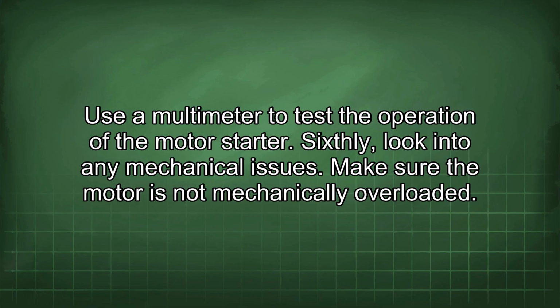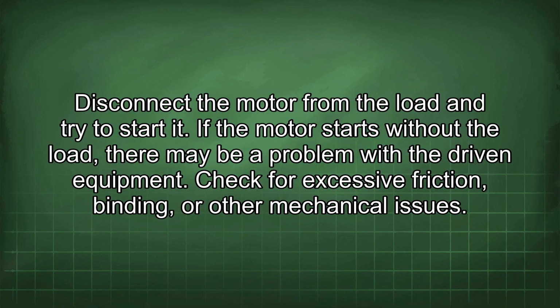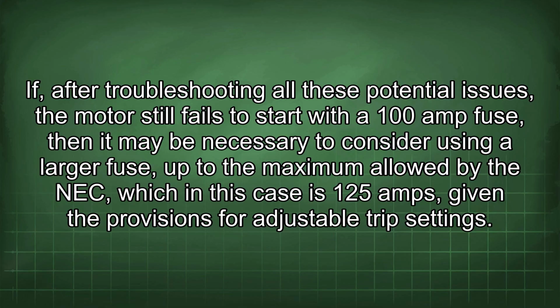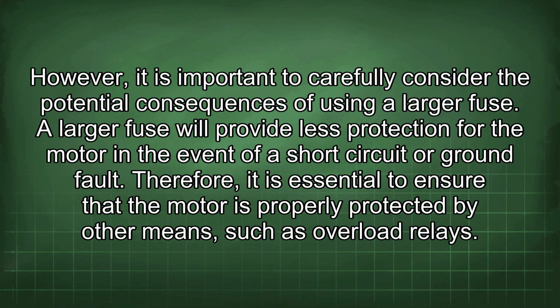Sixthly, look into any mechanical issues. Make sure the motor is not mechanically overloaded. Disconnect the motor from the load and try to start it. If the motor starts without the load, there may be a problem with the driven equipment. Check for excessive friction, binding, or other mechanical issues. If, after troubleshooting all these potential issues, the motor still fails to start with a 100 amp fuse, then it may be necessary to consider using a larger fuse up to the maximum allowed by the NEC, which in this case is 125 amps, given the provisions for adjustable trip settings. However, it is important to carefully consider the potential consequences of using a larger fuse.